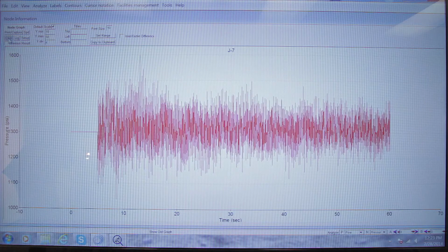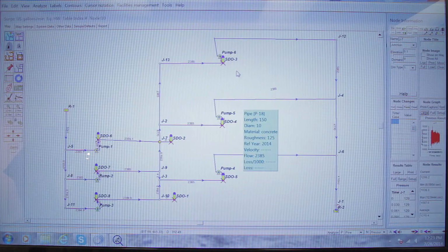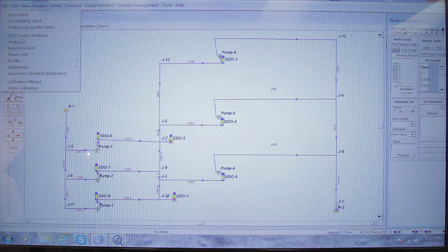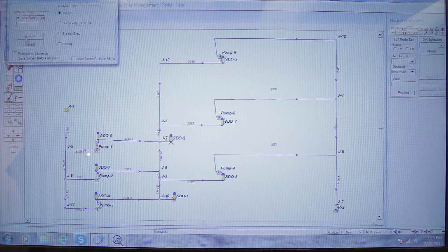So again, in this scenario, we see the worst case scenario is tripping the injection pump, and we look at ways of accepting energy. If you look in our model, and again, I have multiple pumps here, I've put in a solution to protect my low pressure piping. Let's see what happens.